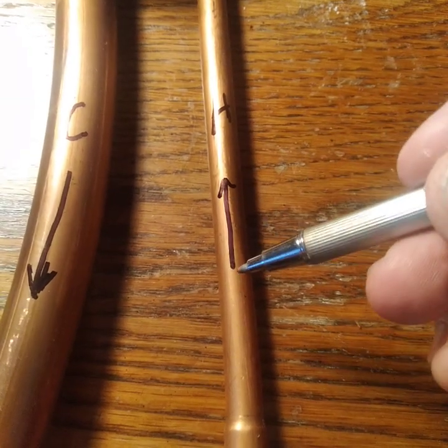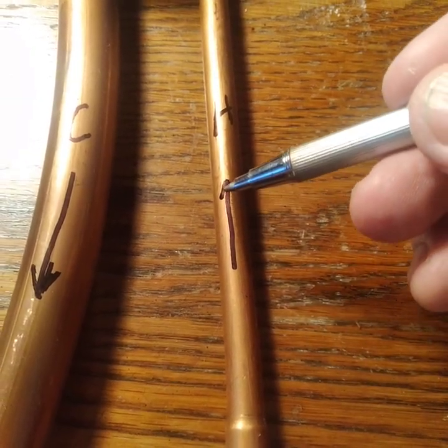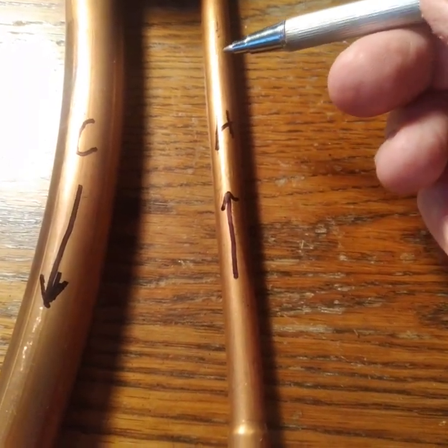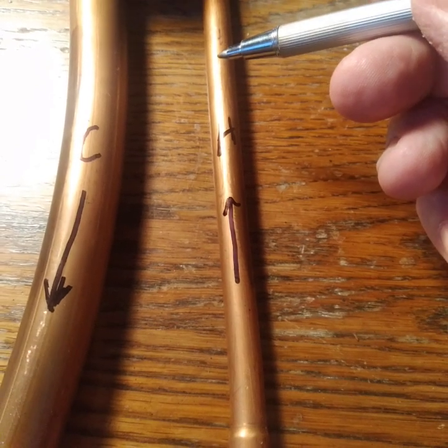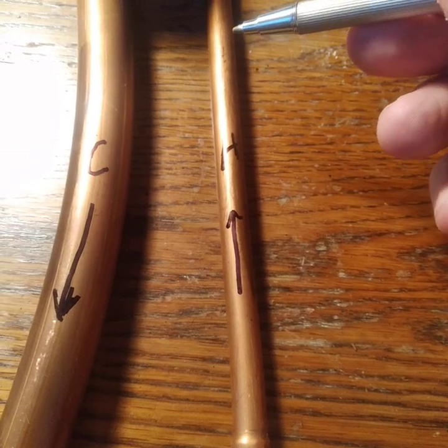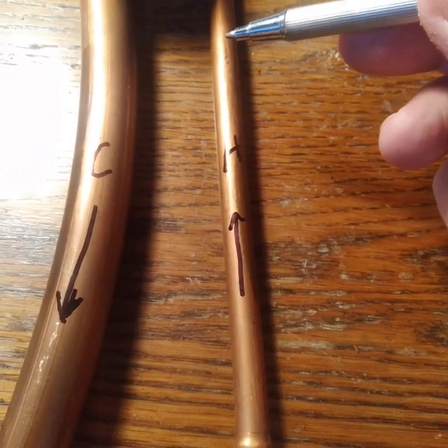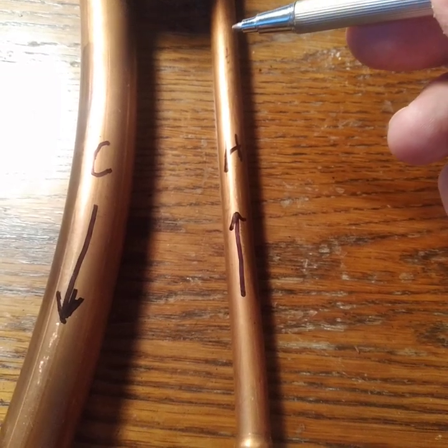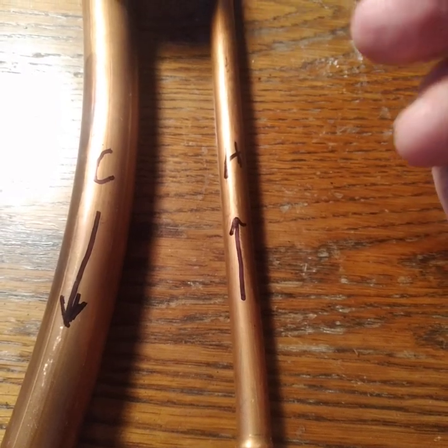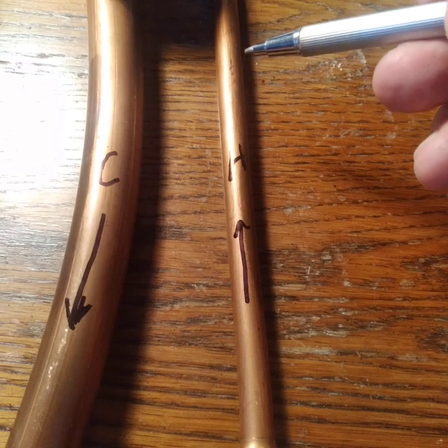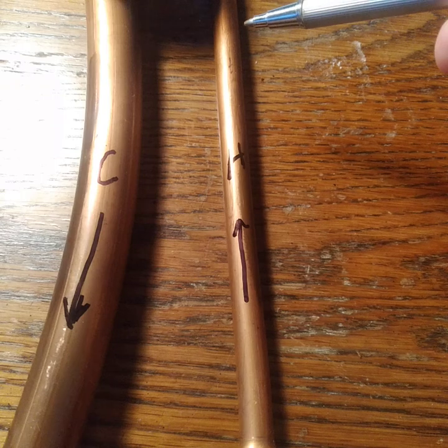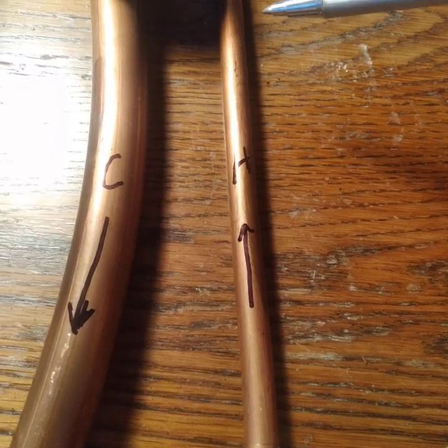So then this refrigerant will travel in this direction, and it goes back inside to the air handler, goes through a TXV or a piston, then it starts to flash, or whatever nomenclature one would like to use, and it goes from liquid to vapor and then all the way to vapor. It goes through the A coil, and once it goes through the A coil, the air comes across there. It pulls the hot air from the room through the return vent across here.